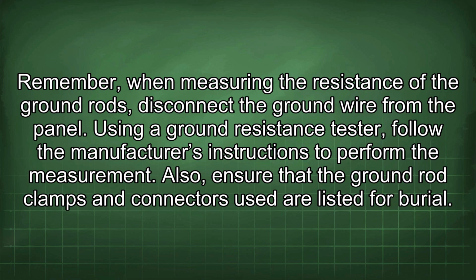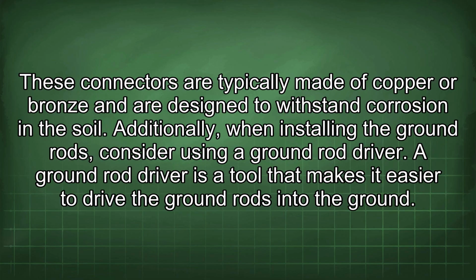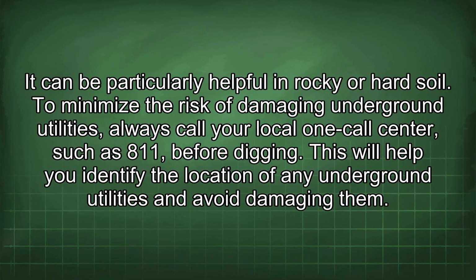Also, ensure that the ground rod clamps and connectors used are listed for burial. These connectors are typically made of copper or bronze and are designed to withstand corrosion in the soil. Additionally, when installing the ground rods, consider using a ground rod driver. A ground rod driver is a tool that makes it easier to drive the ground rods into the ground. It can be particularly helpful in rocky or hard soil.